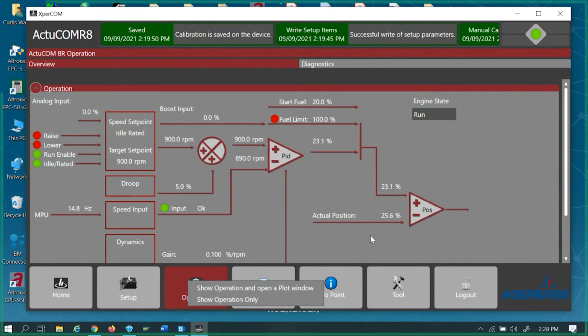Well, I'm not at 900. See how it's starting to open up again, trying to give it some more fuel because I'm below my set point. So let me add some RPM to it, and I want to shoot over it. It's at 960. Guess what? Now I'm turning around, I'm shutting it off. And you've noticed the farther away you get, the faster it's going to react from that set point.